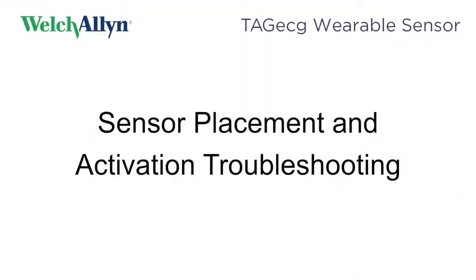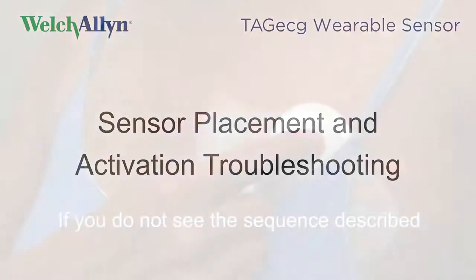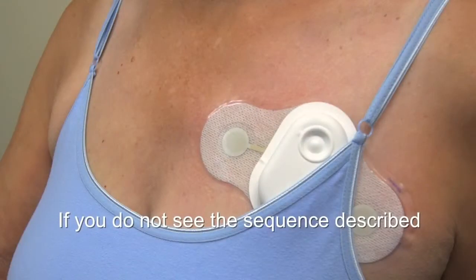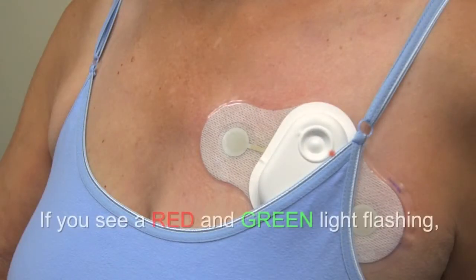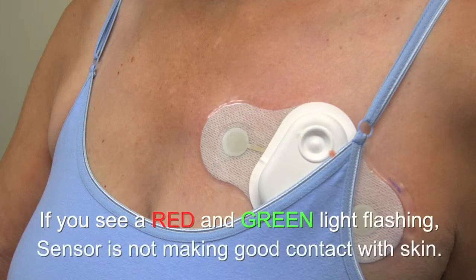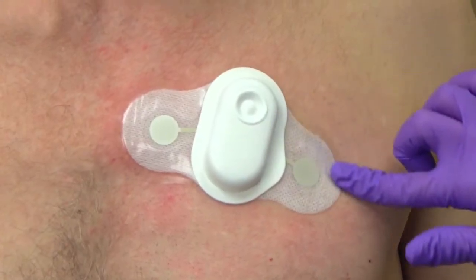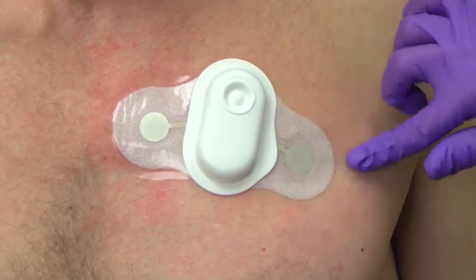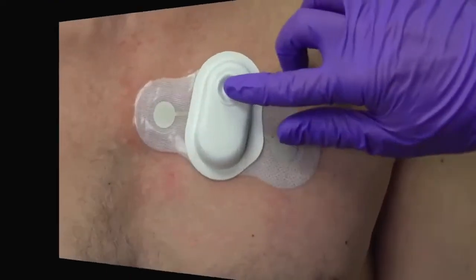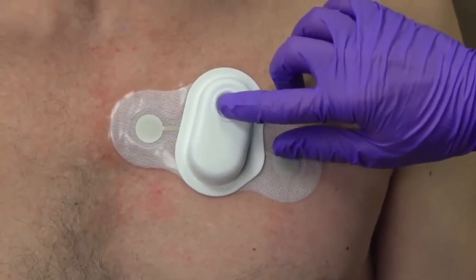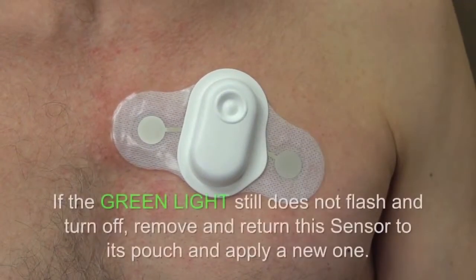Sensor placement and activation troubleshooting. If you do not see the light sequence as described, or if you see an alternating red-green light flashing sequence, the device is not making good contact with the patient's skin and has not been activated. Press down again over and around the sensor and the surrounding adhesive. Wait a few minutes and repeat the button push above. If the green light still does not flash and turn off, remove and return this sensor to its pouch and apply a new sensor.